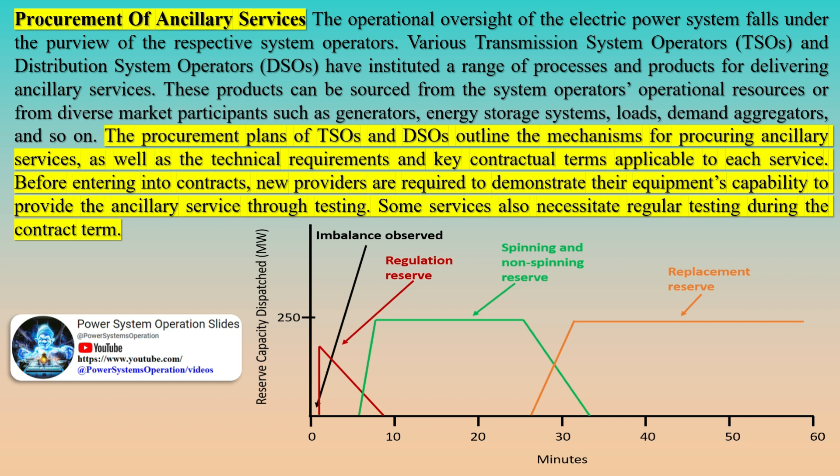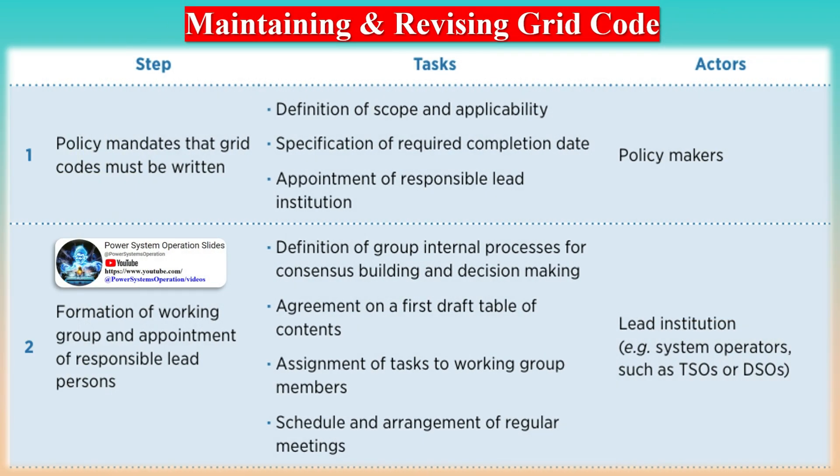Voltage support services are necessary to maintain the voltage of the electric power system within prescribed limits during normal operation and disturbances. This is achieved by balancing the generation and consumption of reactive power. The primary objectives of these services are voltage profile management and voltage stability maintenance. System restoration support services are required to restore the electric power system to normal operation following a blackout, and include black start and islanding operation.